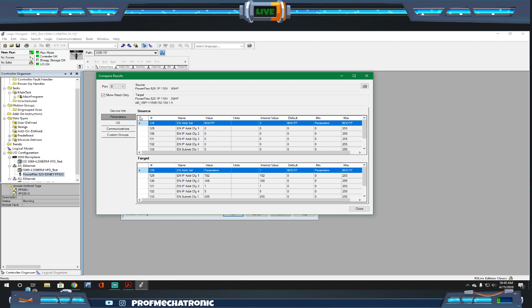So it says there's differences found between our project and the drive itself. How would you like to proceed? Right? So we have upload, we have download, and we have show differences. If we click on show differences, we can have a look here and see what the actual differences are between the drive and the setup. You can see that there's a whole bunch of information between the source and the target. So our target, which is our drive itself, currently has this information in it. And our source, which is our PLC, currently has this information for the drive.